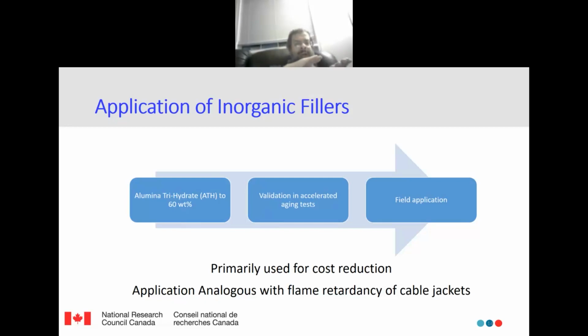First, once you start to have an arc, as the material ages with time it gradually loses its hydrophobicity, and then there will be some arcing on the surface. Once arcing starts, the ATH releases what we call the water of hydration, since ATH is composed of alumina and water particles. Once they release the water, it quenches the arcing, so this mechanism helps reduce the effect of arcing. Second, it improves the thermal properties during arcing.